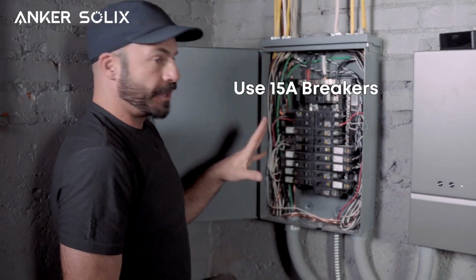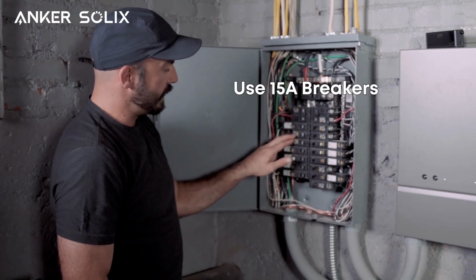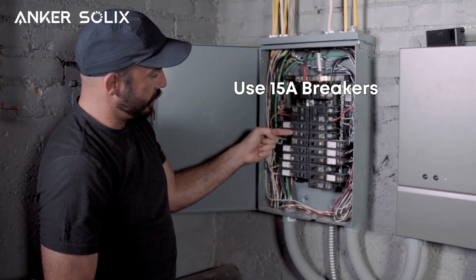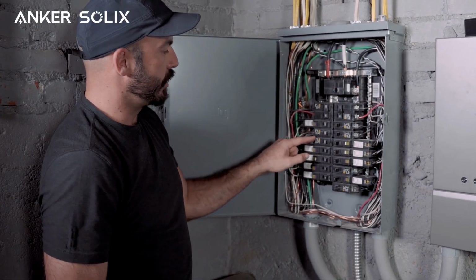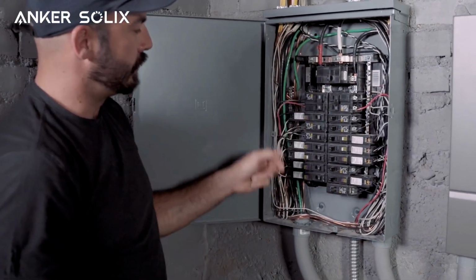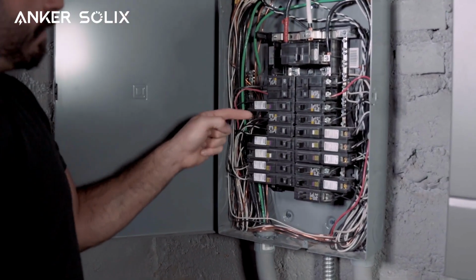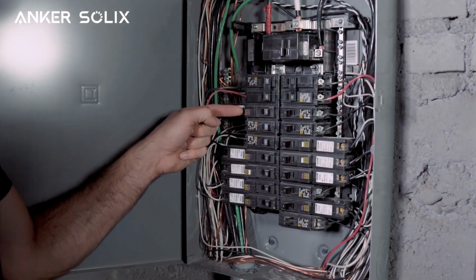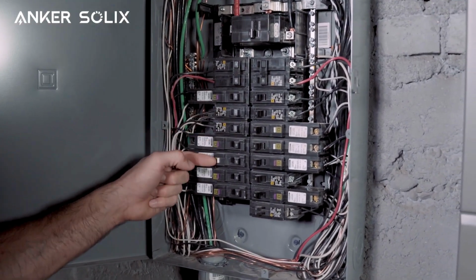When selecting the breakers to use, we'll go with 15 amp breakers, and by choosing ones next to each other we'll make sure we connect to both L1 and L2, because in a typical breaker box the breakers alternate L1 and L2 as their supply as you move down.